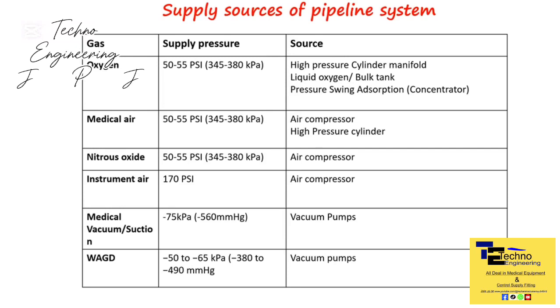Waste anesthetic gas disposal or scavenging systems are used in hospital anesthesia evacuation procedures. Although similar to a medical vacuum system, scavenging systems do not need to be as powerful as medical vacuum systems, and can be maintained around -50 to -65 kilopascals.